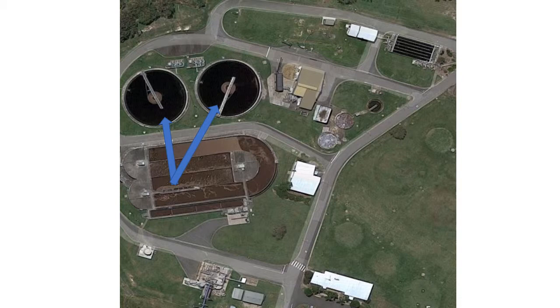During the process of nitrification and denitrification, coagulants and flocculants are added to the water to have the suspended solids clump together, which is the coagulant, and sink in the liquor, which is done by the flocculants. Once the activated sludge has passed through the aerobic tanks and completed denitrification and nitrification processes, it is then gravity fed into the secondary settling tanks.